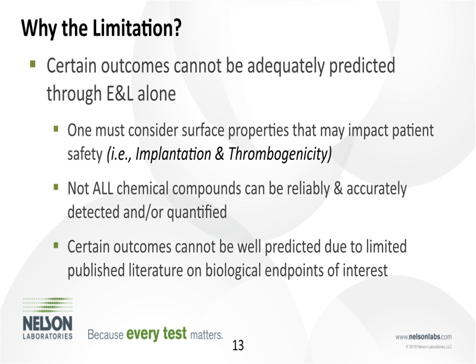Also, we have a limitation that not all compounds can be accurately detected. This could be a novel compound that releases from your device and is maybe not found in the instrument's library. Therefore, we cannot identify it. Another limitation is if it is a novel compound and we do not have a standard that is commercially available, we will not be able to quantify the amount coming off of the device.